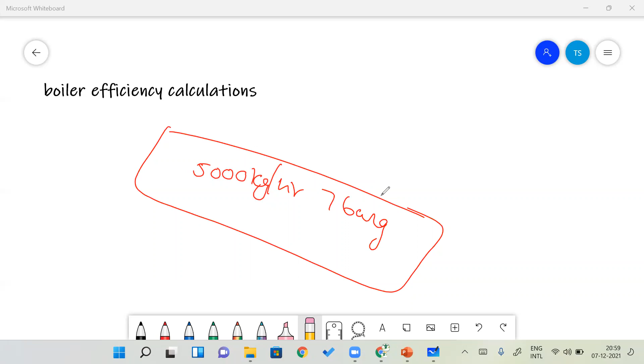Now, the capacity of a boiler is mostly considered as production rate at a specific pressure. For example, the steam I am generating is 5000 kg per hour at 7 bar gauge. This is how you have to explain boiler capacity. When somebody asks what the boiler capacity is, you say 5000 kg per hour at 7 bar gauge pressure, not just 5000 kg or just 7 bar gauge. The pressure and the rate per hour are very important things.